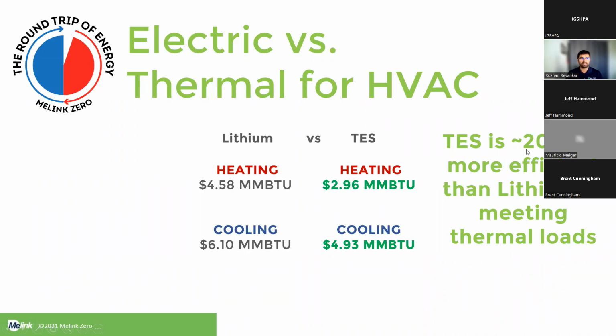I want to point out that thermal energy storage doesn't necessarily reduce energy consumption. It helps a lot to drop the peak demand for the entire system. Because thermal energy storage is essentially just storing energy, you're spending energy to create it, store it, and then use it back. So you're not reducing overall energy consumption, but by shifting the peaks you're able to reduce peak demand for a particular system and building.